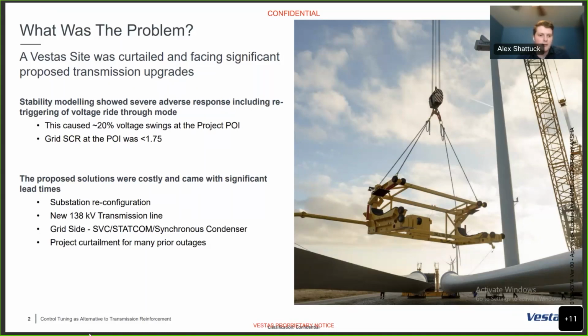So usually when this happens, the first thing that gets suggested is that we have to do some transmission upgrades. The reason for that is, a lot of the times either a generic model gets used where you might not be able to put those solutions back into the product, or the OEMs don't usually jump into the situation and try to provide solutions. So usually at this point, the model is taken as is — the plant stability model — and the performance is taken as is.